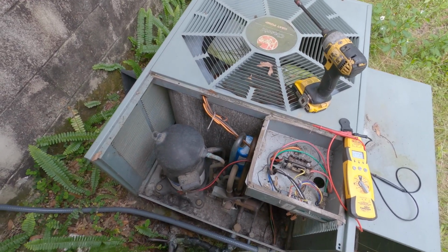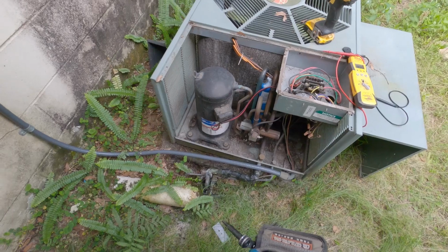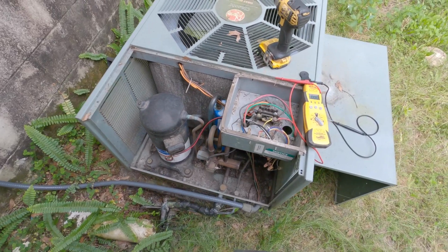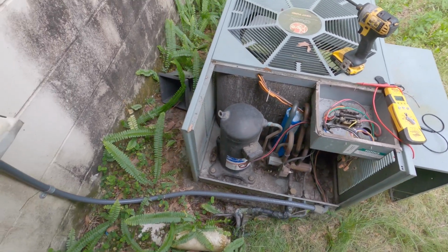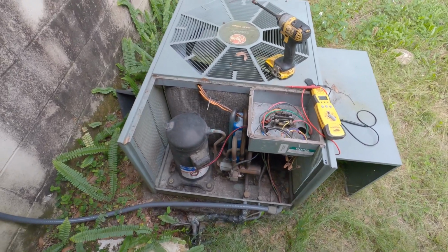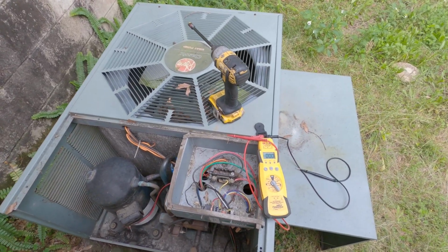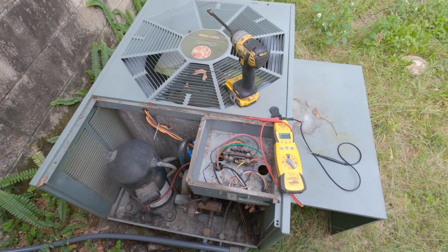They just keep running and running until they rust out pretty much, or compressor fails and customer doesn't want to put that much money into it, or they can't because it's R22. So we're gonna get a contactor, put it in here, and see what happens. Okay, so we've got a bad contactor, but this unit is extremely old. So when I run into something like this, instead of me just changing the contactor out and testing it out, because it could be a waste of time, I'm gonna go and do an inspection on the whole system here.